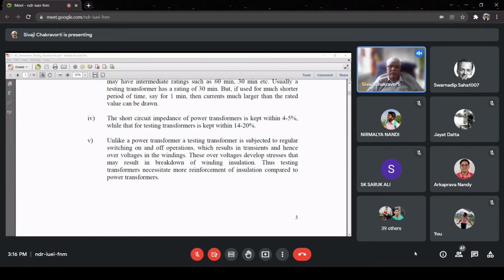When a transformer is manufactured, there is no such power system it is tied to. A transformer can be used in a factory, but still the impedance will be given as a percentage. So what does percentage mean? There is something in the numerator, something in the denominator. So what is in the numerator? What is in the denominator? Base values are basically the rated values. Correct. This is number one. But which rated value? There is voltage, current, power. Which value?